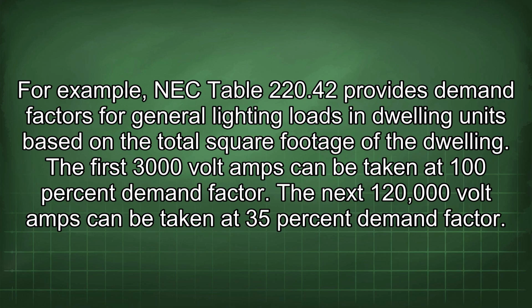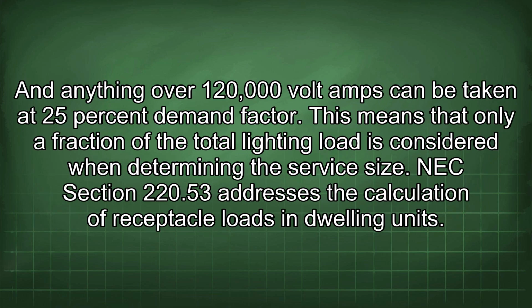For example, NEC Table 220.42 provides demand factors for general lighting loads in dwelling units based on the total square footage of the dwelling. The first 3000 volt-amps can be taken at 100% demand factor. The next 120,000 volt-amps can be taken at 35% demand factor. And anything over 120,000 volt-amps can be taken at 25% demand factor. This means that only a fraction of the total lighting load is considered when determining the service size.